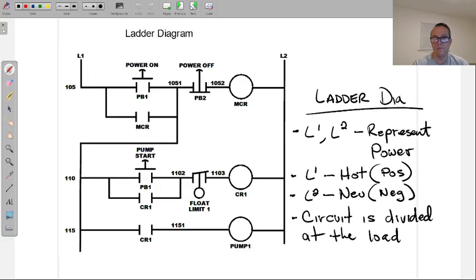Looking at the pump now. Pump hasn't started, uh-oh, pump's not working. Well, why hasn't this contact closed? Well, this thing should have gotten power. Relay coil, that is a normally closed float switch. Is it open? If that's open, then no power down the line. All right, so that's the beginning.